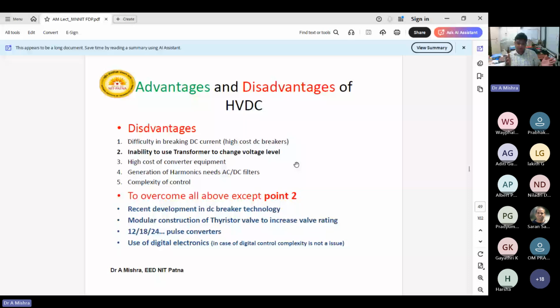Some beauty is there, but this is a limitation: there is nothing like power flow control in the transformer. If you are going for the DC side, it is possible because you are able to control the output voltage and output current by changing the firing angle. So the transformer is one of the good things. It is doing its job, but it does not have any kind of power flow control inside the transformer.